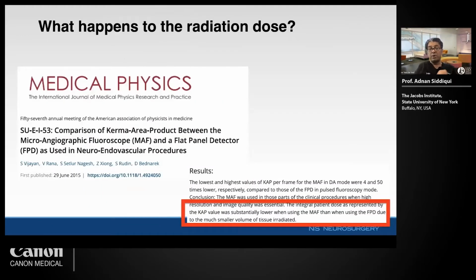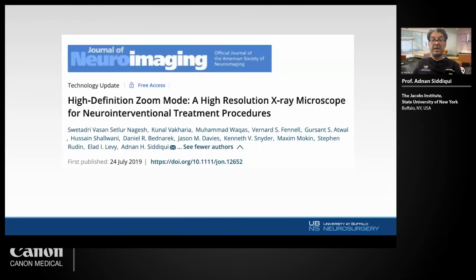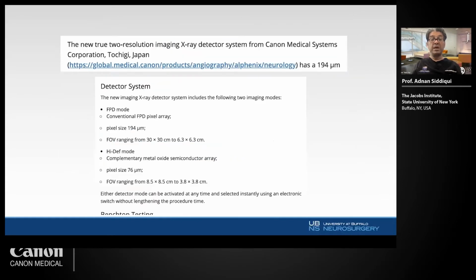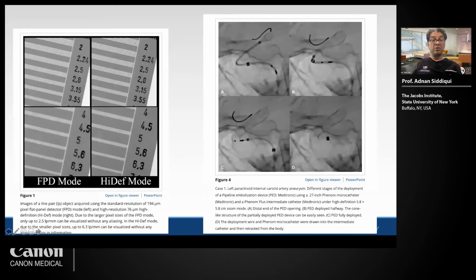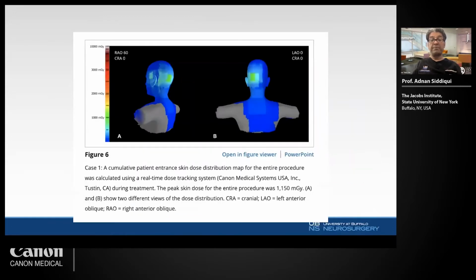So the question then became, well, what happens to the radiation dose? That was the first thing: you must be radiating them. The point is that when you have the integral patient dose based on the KAP value, it's a lot lower because of the much smaller volume which is being irradiated. The best example for this is that it is a high resolution X-ray microscope, just like the one I have in the operating room. This makes it quite unique, where you have pixel size compared to a flat panel of 194 down to a 75 micron resolution. That gives you a lot more detail that you would not be able to otherwise garner. And the radiation dose becomes a lot better based on the fact that you're going for a much, much, much smaller area than you would otherwise.